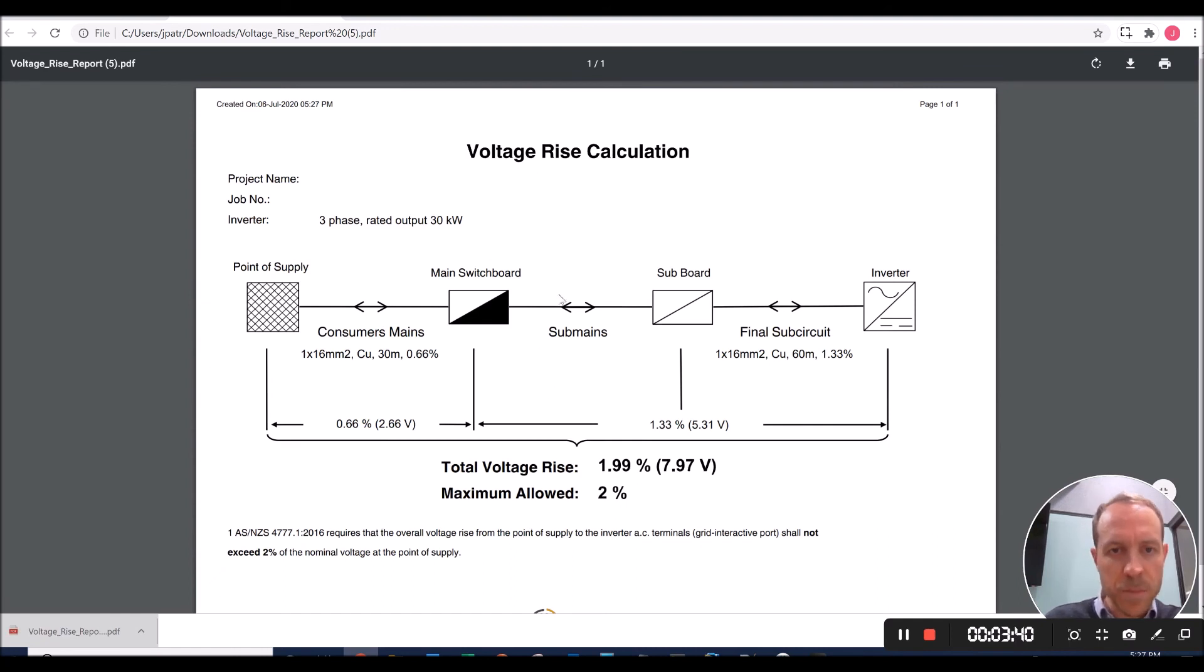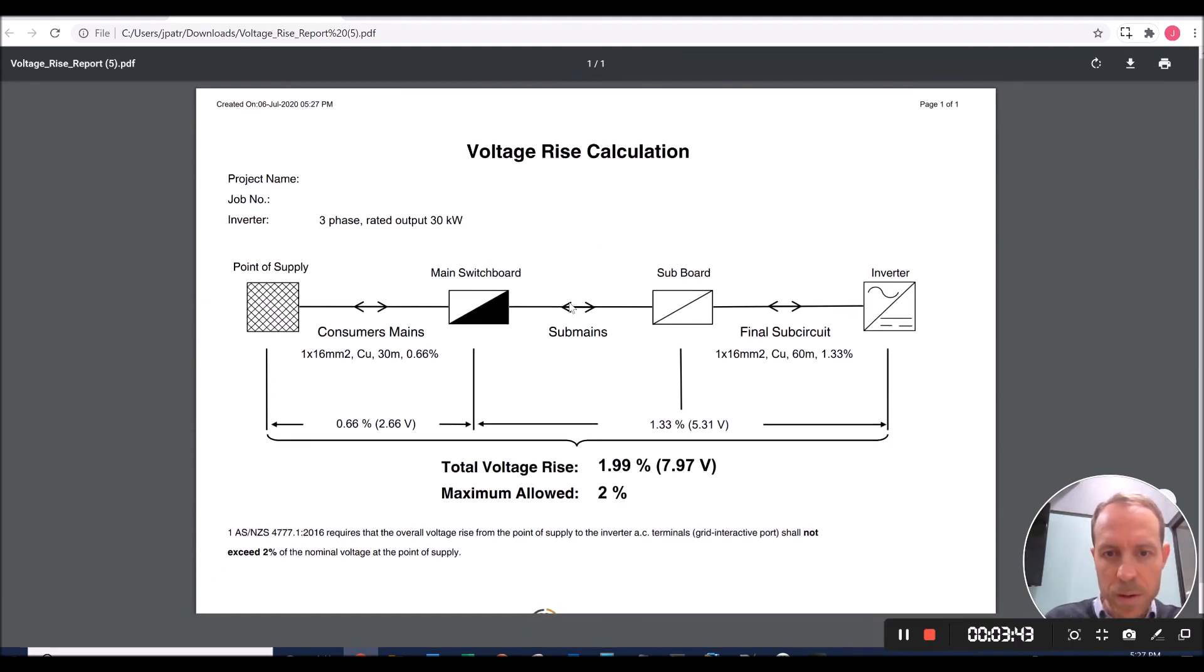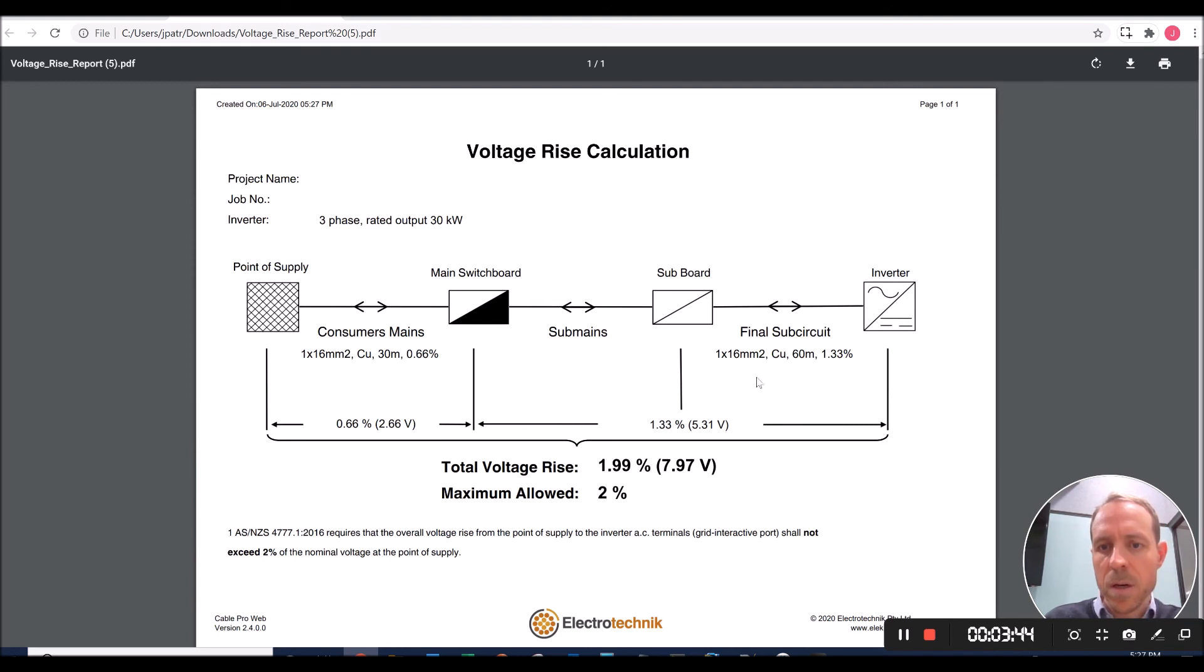Here we have a customized voltage rise report for our installation, showing that for the final sub-circuit, which is connected to the inverter, we've got our 1 by 16 square millimeter copper cable over 60 meters. The voltage rise is 1.33% for that section.